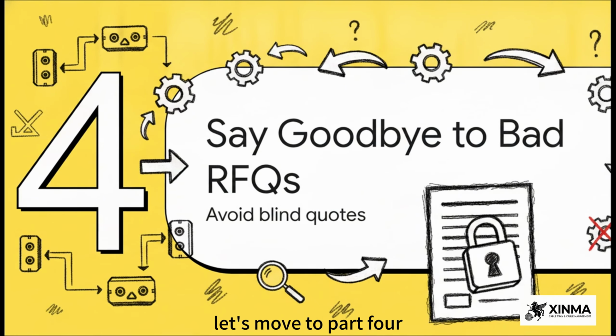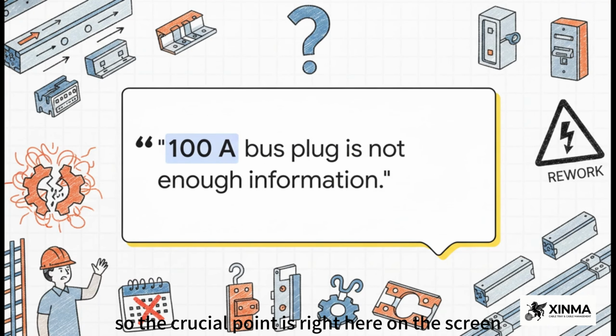Let's move to Part 4, saying goodbye to invalid RFQs. So the crucial point is right here on the screen. Frame geometry, stab arrangement, latch design, and interlocks must be verified before sourcing. Why? Because as we established earlier, 100 amps is never enough information. If your request for quote only lists amperage, you're getting a blind quote. It's really that simple. And this kind of incomplete RFQ leads directly to absolute disasters on the job site. We are talking massive installation delays, wildly expensive rework, and severe safety hazards. Just don't do it.